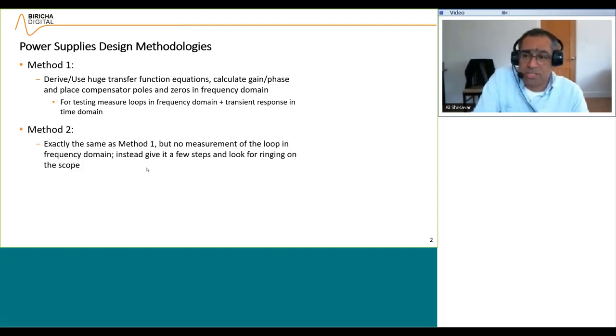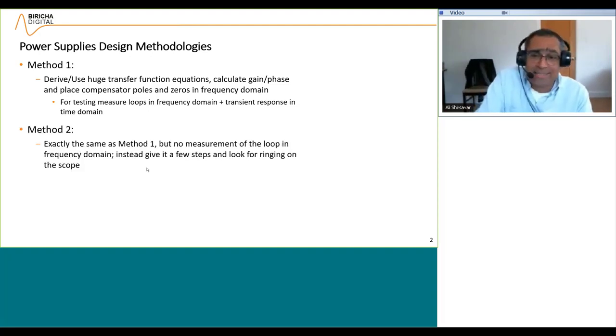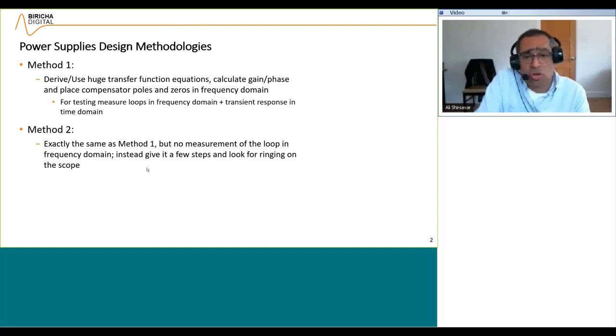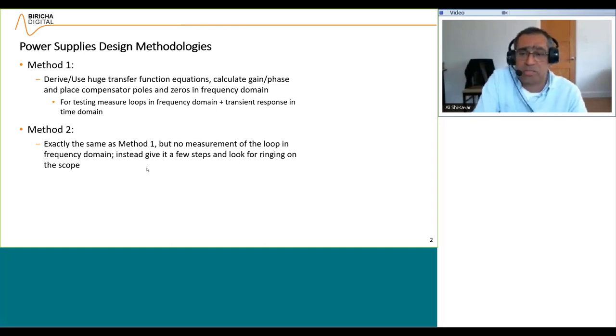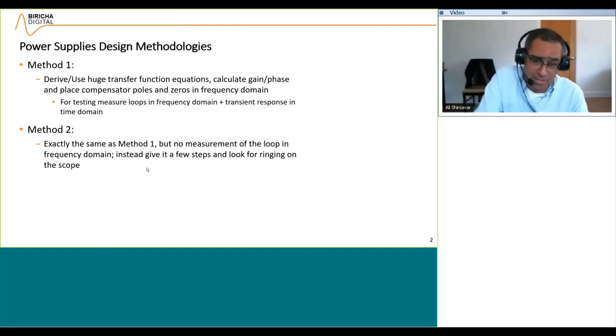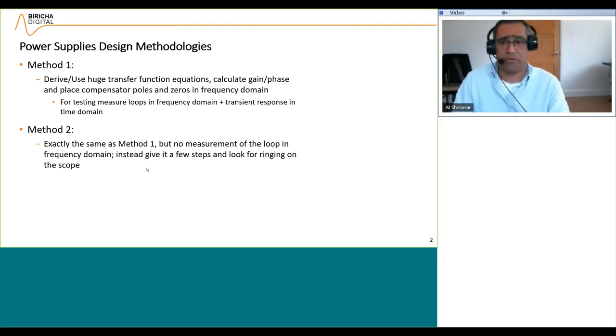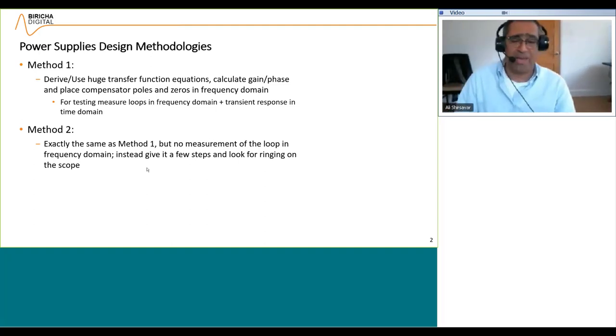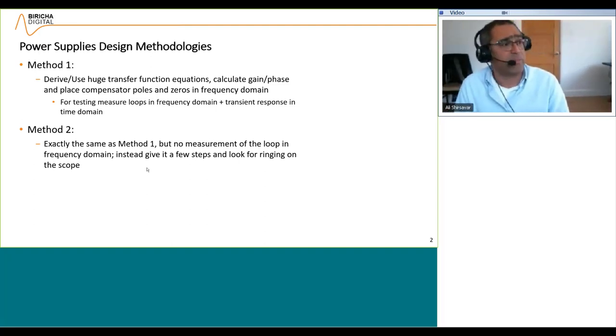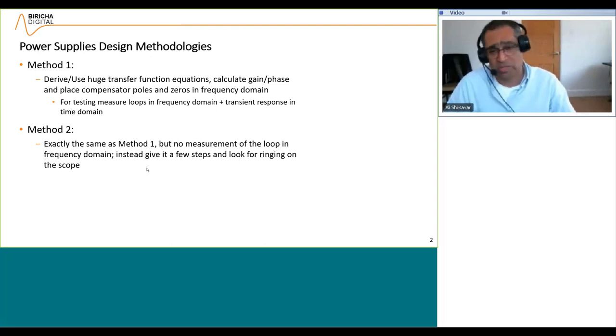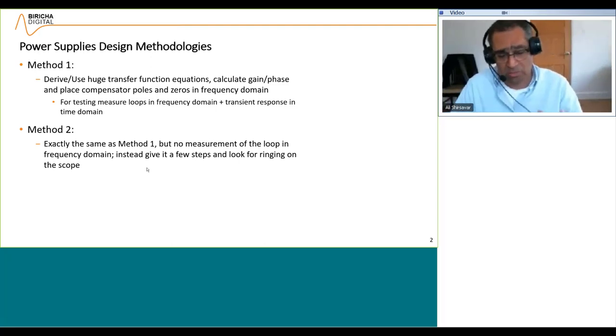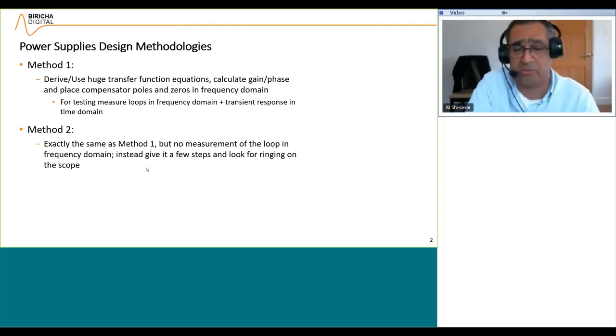Then we have method two, which is exactly the same as method one, but you don't measure the loop in the frequency domain. Instead you just give it a few steps and you look for ringing on the scope. We don't recommend you do it that way — measuring the loop is always the best way to give you the most amount of information.